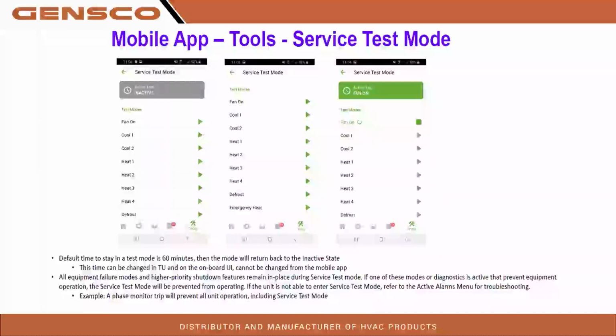Service test mode, again, this is Bluetooth, so it's only good for about 25 feet. So unfortunately, you have to stay near the rooftop unit. Once you put it in test mode, you have cool 1, cool 2, defrost, emergency heat. If you've got an economizer, it'll have test economizer. Default time in test mode is 60 minutes. Then the mode will return back to inactive state. So if you do forget to take it out of test mode, it'll reset in 60 minutes.